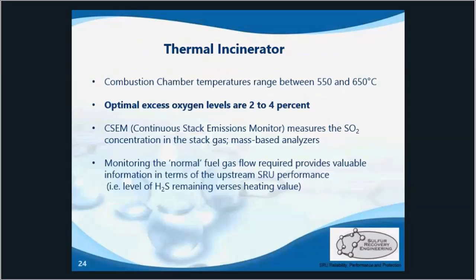Higher fuel gas usage and the coinciding CO2 production is associated with excess oxygen, so optimal levels for oxygen in the stack are 2-4% O2. Oxygen analyzers do have a poor track record due to the acidic nature of the stack gas, so knowing our normal fuel gas flow requirements is important because the more sulfur species remaining in the tail gas, the more fuel gas will be needed to convert it to SO2.